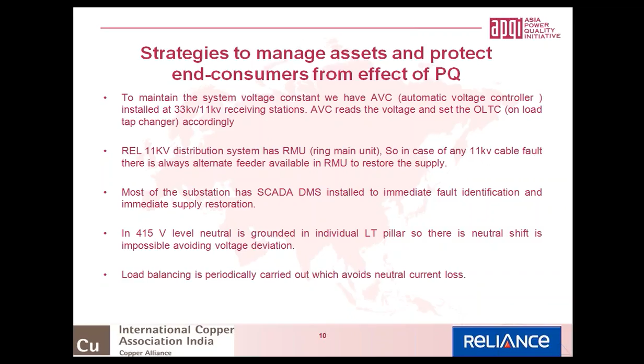We have introduced neutral ground at individual LT pillars, so that whatever harmonics or voltage deviations are observed, everything gets grounded at that point rather than having the ground at the substation level. We measure the load balance, that is R, Y, B. If there is a total imbalance within the load, then we try to segregate the load so as to have a balanced load.